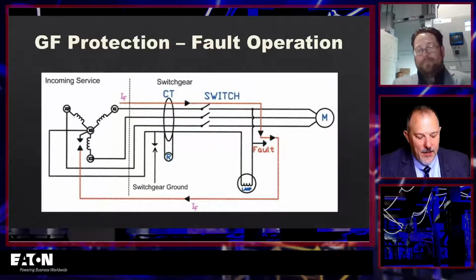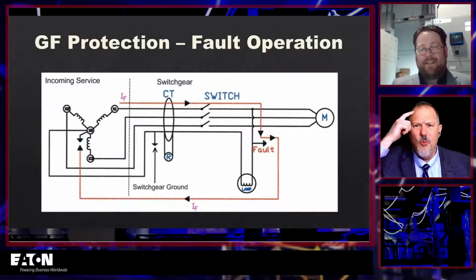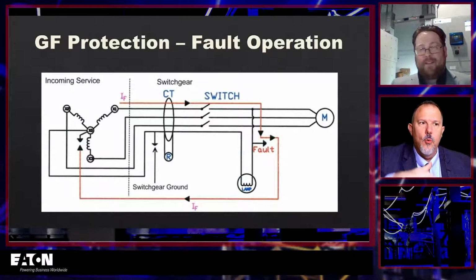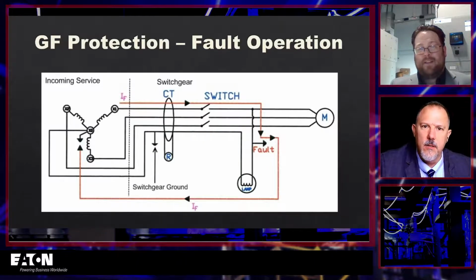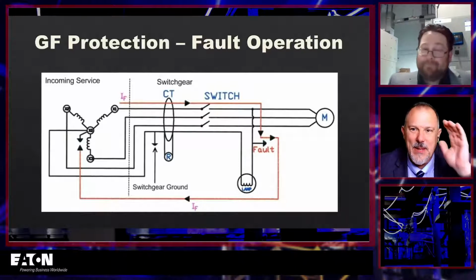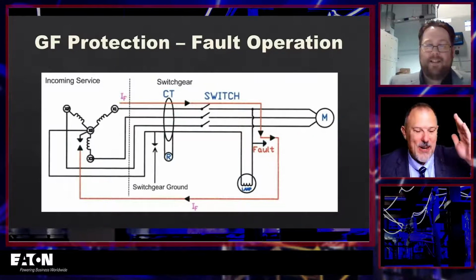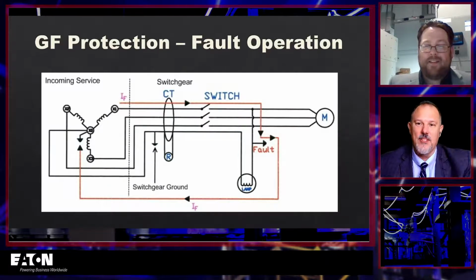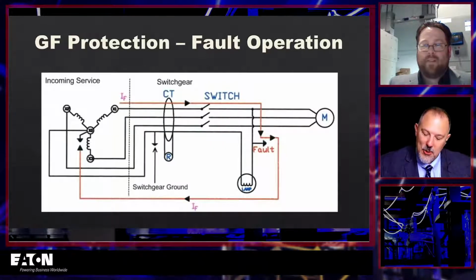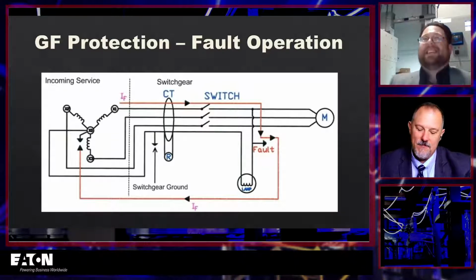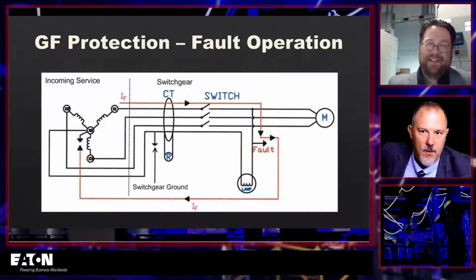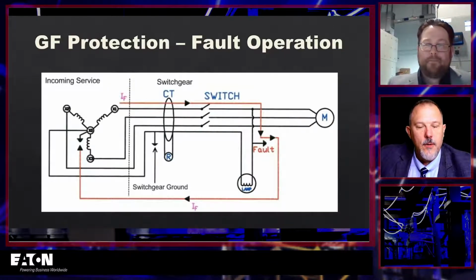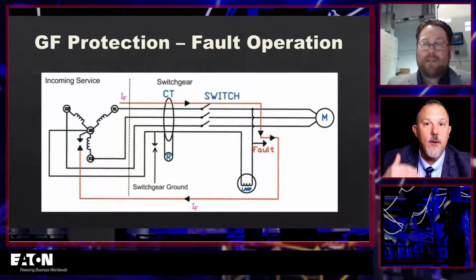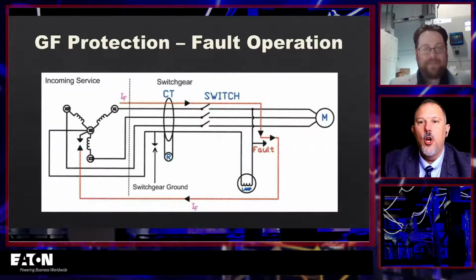Okay, and I'll tell you, this was a while ago. I scratched my head and said, "Why? I don't get it. Why would I have to increase my equipment grounding conductor?" I mean, from an engineering perspective, I'm like, why? Right? So I asked people on Code Panel 5. I asked Chuck Mello. I talked to Vince Saporita, and you know what? I got two basic answers. One was, and I had a very astute gentleman who pulled me aside, put his arm around my shoulder, and he says, "Thomas, don't you know that when you increase the length of a conductor, you're increasing the impedance, and the fault currents will be very low?" I said, "Yes." He says, "And what happens when you increase the size of that conductor? What happens to the impedance?"